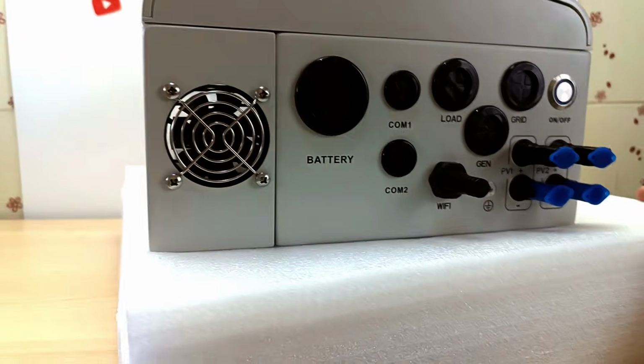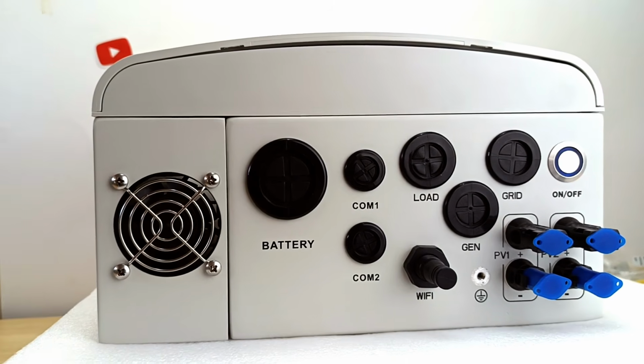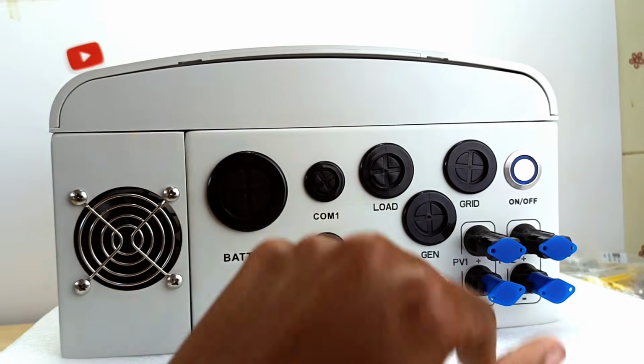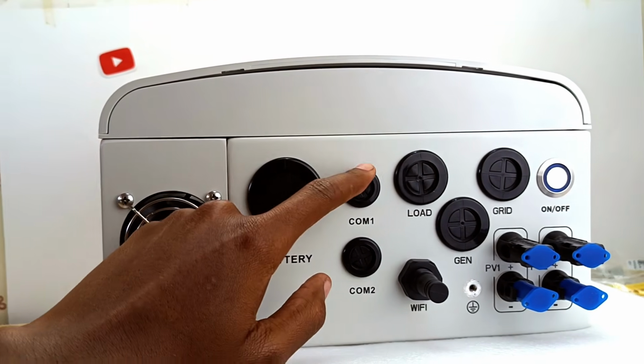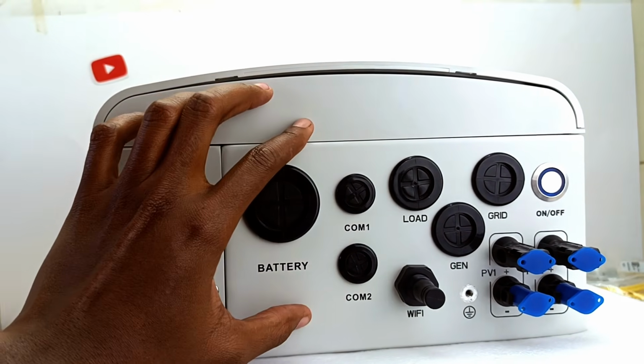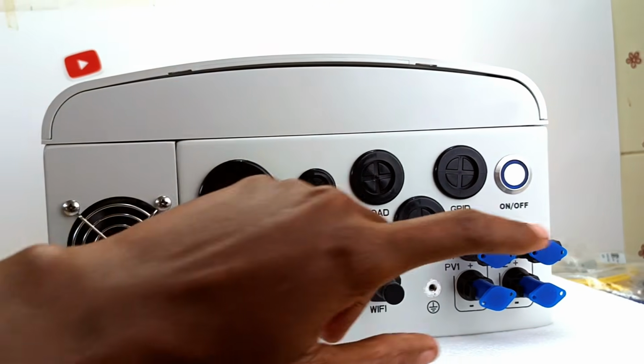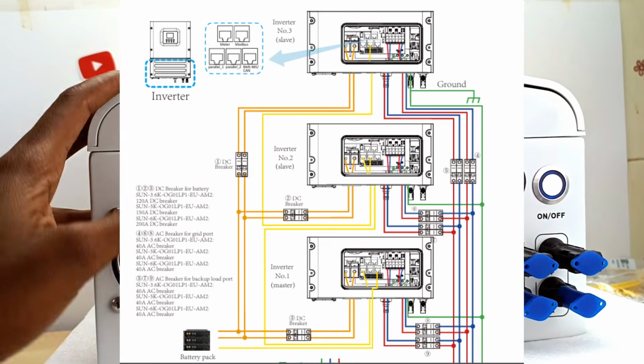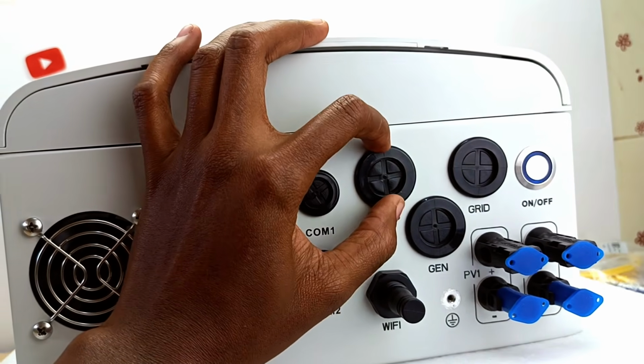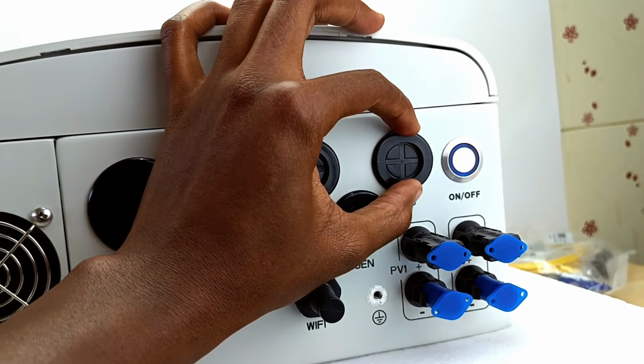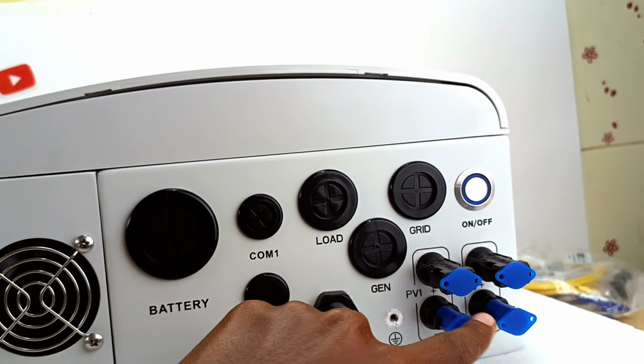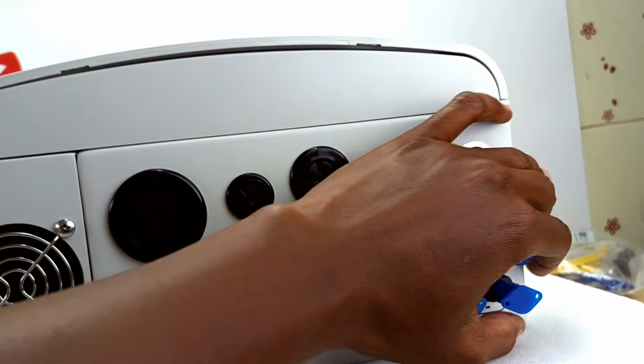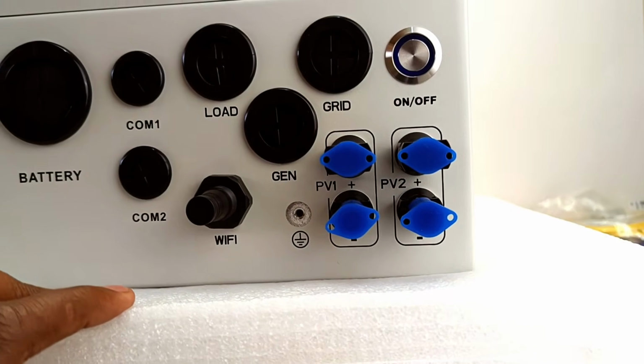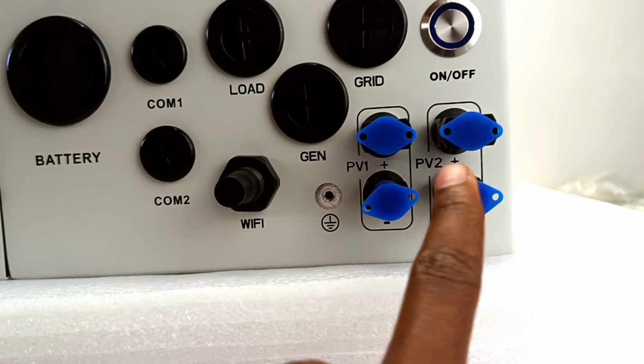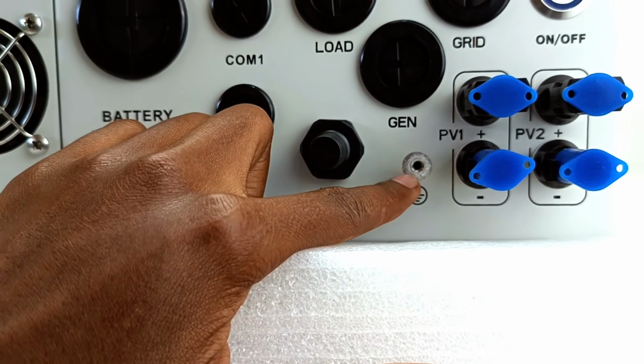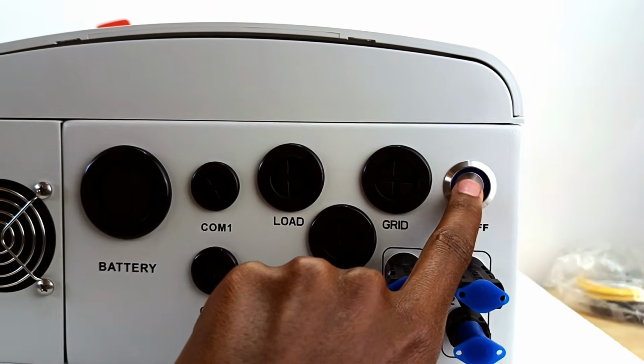So let's take a look at this inverter all round. At the bottom we have the circulation fan as well as all these other connections. The battery cables will go through here. These are for your communication either from the inverter to the battery or from one inverter to another inverter, because you can actually connect these inverters in parallel to one another. The backup load cable will go through here, the generator cable as well as the grid cable. Because this is a hybrid inverter, it has solar as well as connection to the grid. This inverter also has twin MPPT, and that's why you can see it has PV1 and PV2. That's for connecting the protective earth, and that is the on-off switch.